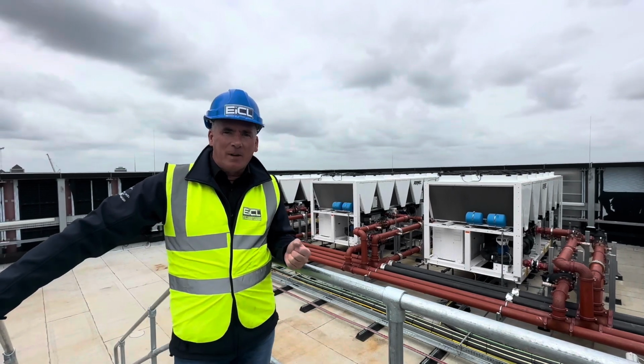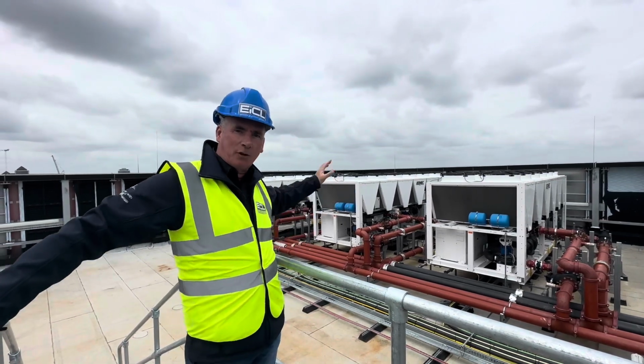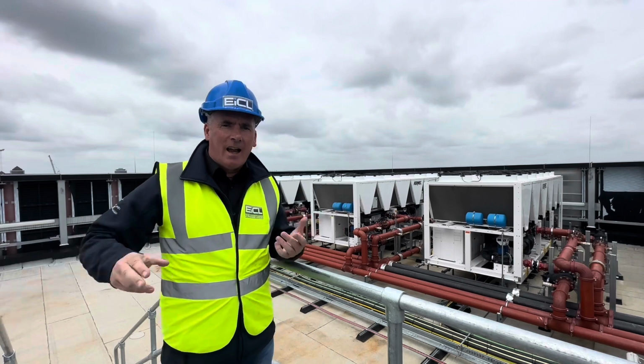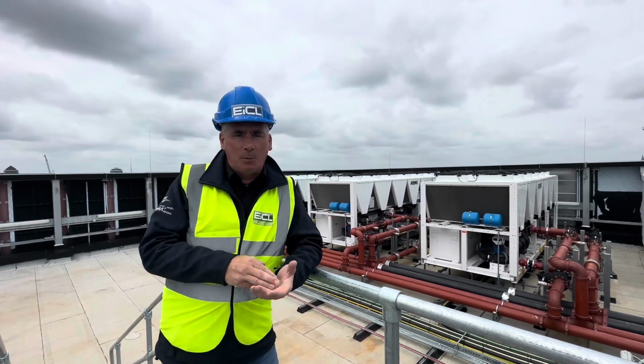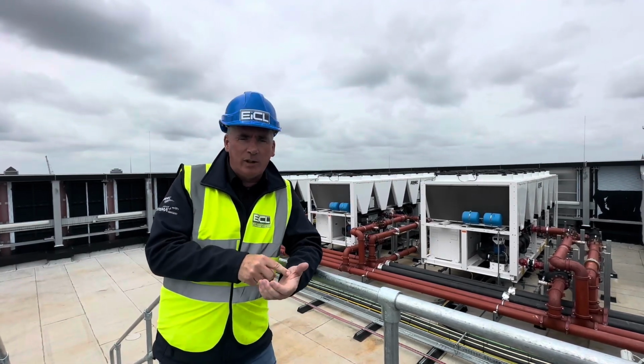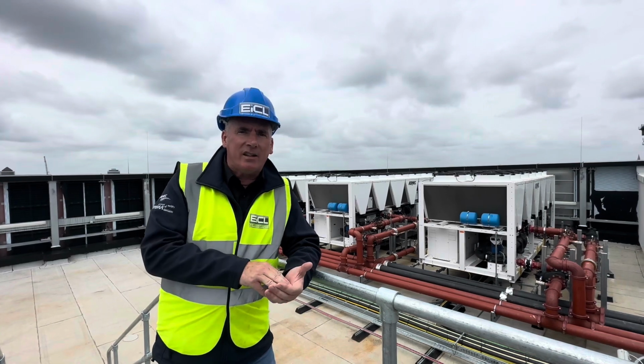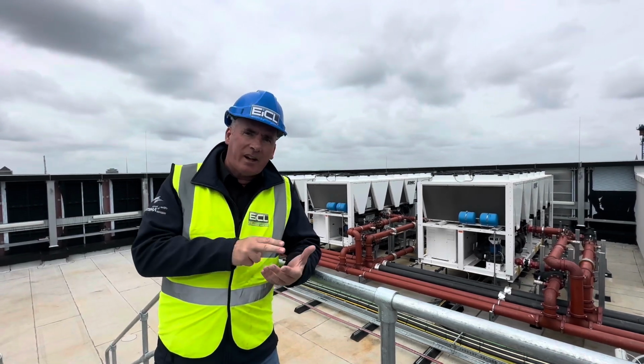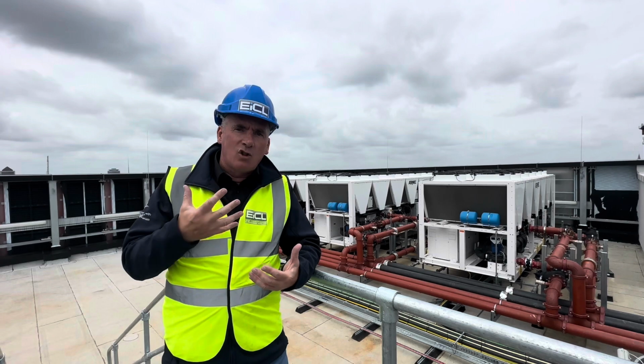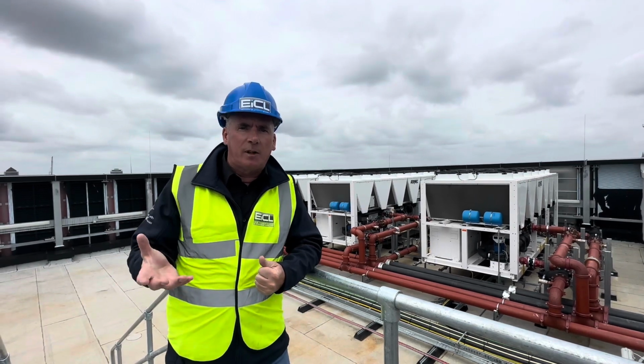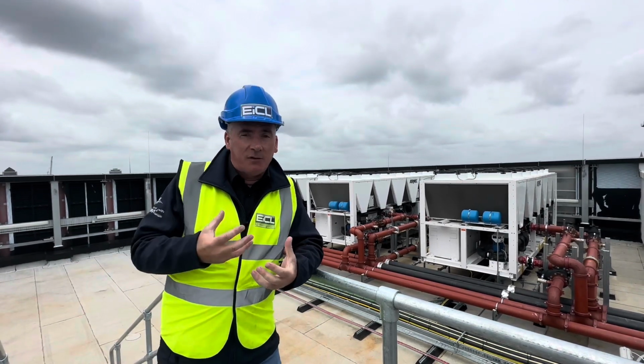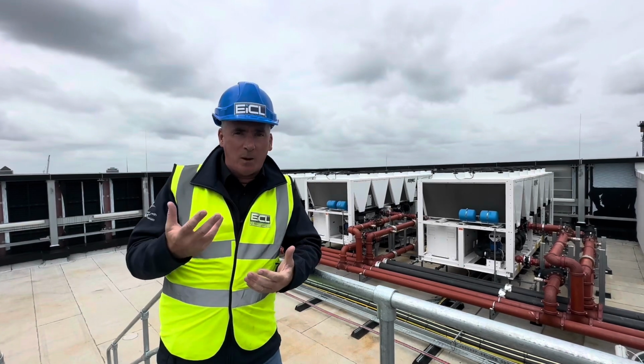Okay, so we're on the rooftop here of Lime Street, and this is where we have our three multifunctional heat pumps. For anyone that's not familiar with the multifunctional heat pump, basically they provide cooling only, heating only, or simultaneous heating and cooling. Obviously, when you're in simultaneous heating and cooling, you're more than doubling the energy efficiency that you would have got typically from a chiller.